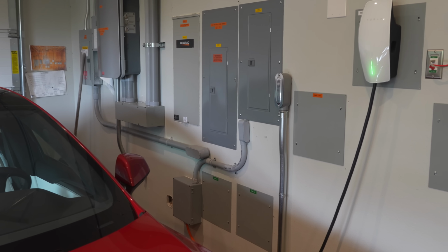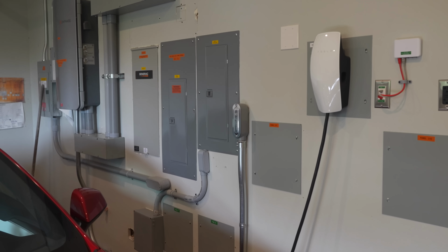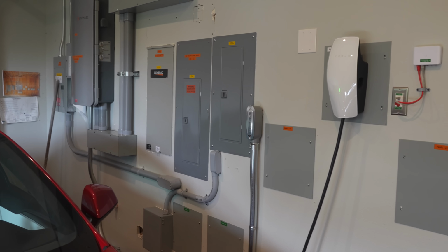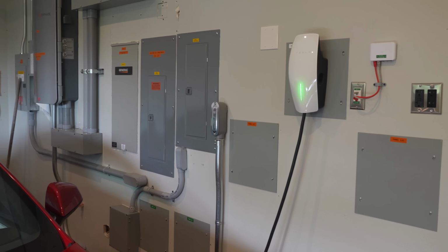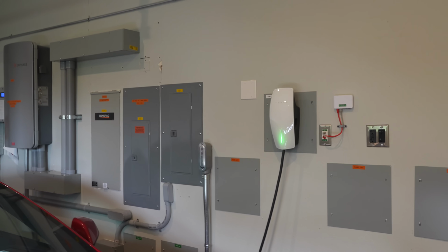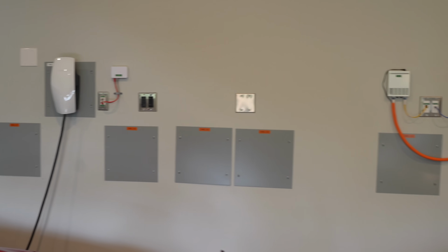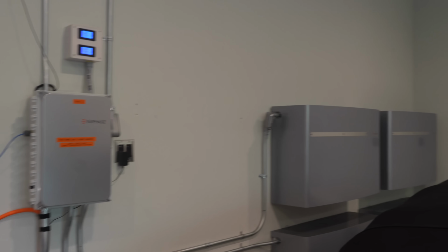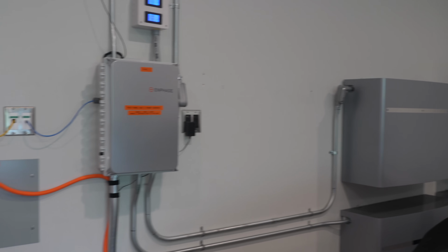So it's a really good system for if you lose main power to keep everything running. You really don't notice it at all. The batteries kick in in about 100 milliseconds, so it's pretty fast. I do have a UPS for the server room, that APC Symmetra, and that's really there to provide the double online conversion that takes AC to DC back to AC to make really clean AC power. That way, if you have dropouts in what's coming over the grid, the power going to the server room is really reliable. But this forms the backbone of what feeds into all of the house power and the server room.